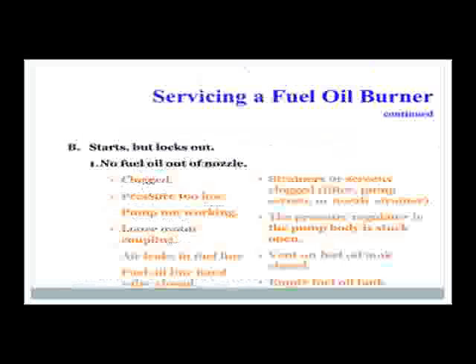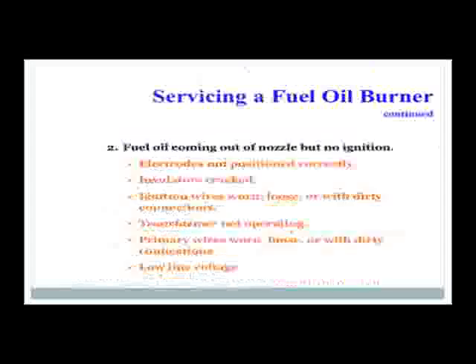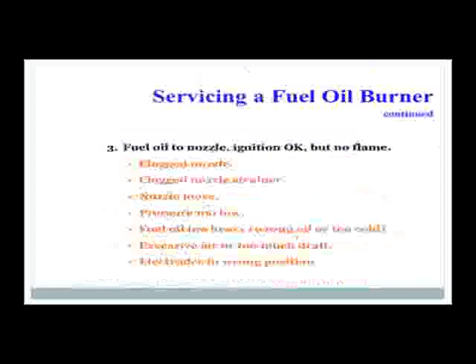If the burner starts but locks out, check fuel to the nozzle. A variety of reasons including clogged nozzles, too low pressures, fuel tank venting, fuel problems. If fuel is coming out of the nozzle but you have no ignition, check your electrodes. Make sure the insulators aren't cracked. Make sure the ignition wires aren't worn, loose, or have dirty connections. Make sure your transformer is operating. Primary wires may be worn, loose, or have dirty connections. You might also have low line voltage.